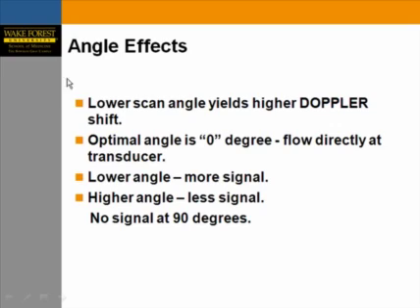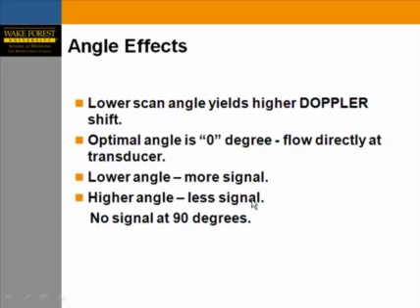The angle of inclination is also important. A lower scan angle gives the best or highest Doppler shift. The optimal angle is zero degrees — the lower the angle, the better the signal; the higher the angle, the worse the signal. At 90 degrees, you get no signal or Doppler shift.